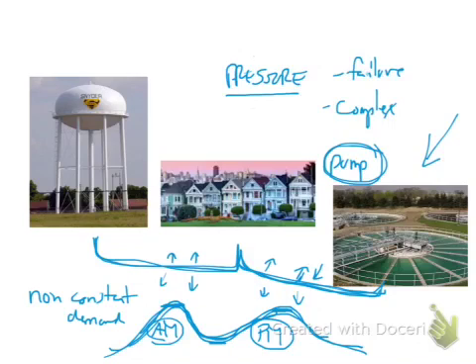Also, the water in your house would slow to a trickle out of the tap. So how do they get around this? They use the water tower. During the trough time, the pump at the bottom of the water tower pumps the water up into the tower, and it sits there until the peak time. At peak time, they let it flow back down. So you have the pump from the water filtration area, and you also have the water flowing down from the water tower, and between the two of them, they maintain the water pressure.